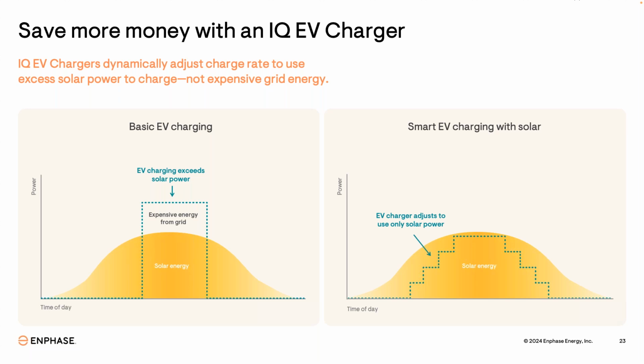The Enphase system can do that because the IQ EV charger is integrated, and the Enphase system is monitoring energy consumption with consumption CTs, or current transformers. So it can actually calculate exactly how much excess solar there is, and it can adjust the rate of charge in 25% steps in order to make sure that we don't draw from the grid.